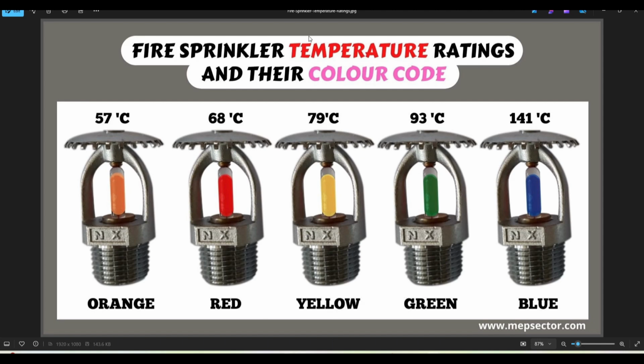Once you give the quantity, he'll ask you what kind of sprinkler you are using. Okay, so we are using 68, 79 and 57. If it's a high hazard class, we are basically not doing that kind of project mostly. If you are, then you have to study further about these things. But suppose you are using these, if the area is air conditioned, then you will go for 68, and if not conditioned, then you will go for the 79. The color will be red and yellow. Of course, this will not show in the software, but somehow you need to put it into the family which you are using in your project, or by naming, whatever way you can segregate it, but you need to know that.